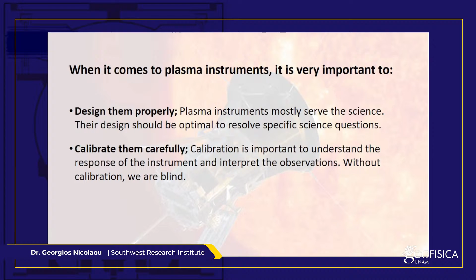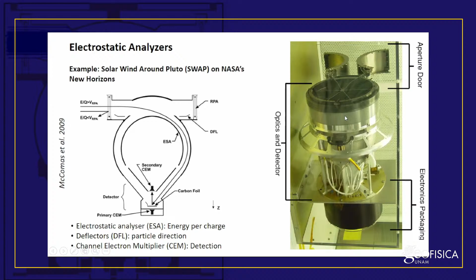So let's go and see some cool designs of typical plasma instruments. So I'm going to refer to the plasma instrument category that is called the Electrostatic Analyzer. And here I use one example, the example of Solar Wind Around Pluto, or for short, SWAP instrument on NASA's New Horizons. This instrument is designed to detect and measure basic properties of plasma ions, actually solar wind ions, that interact with Pluto's environment. So the instrument looks like that. It's like a cylinder, and this silver region around this disk is the aperture. So the particles can enter the instrument to get detected from this region here, around this disk.